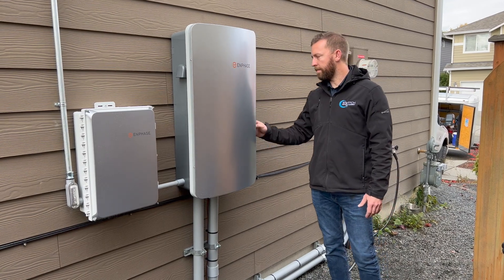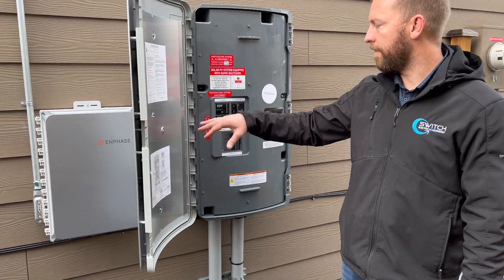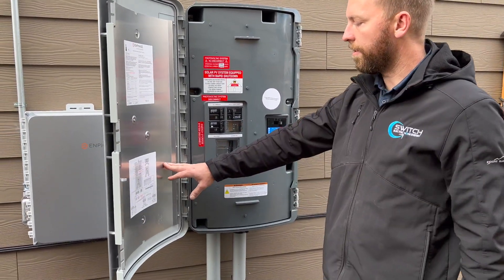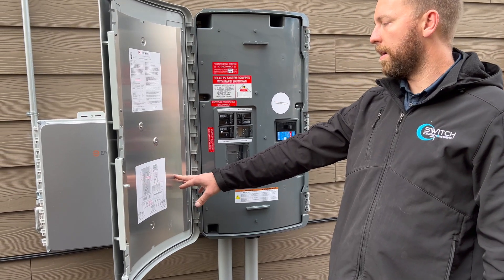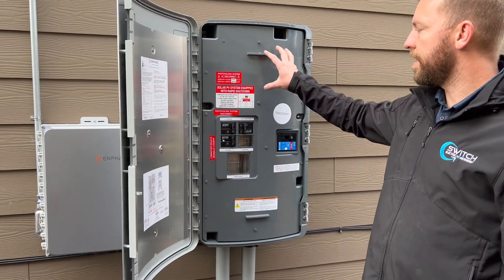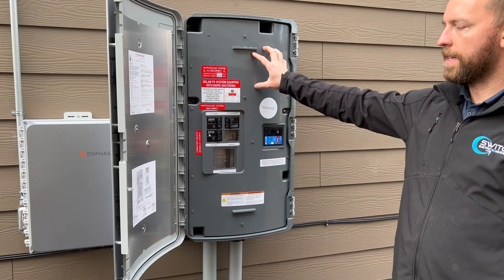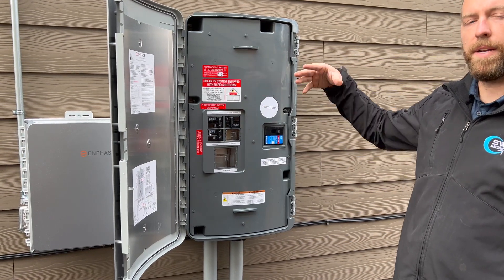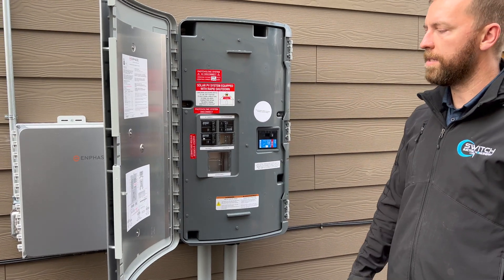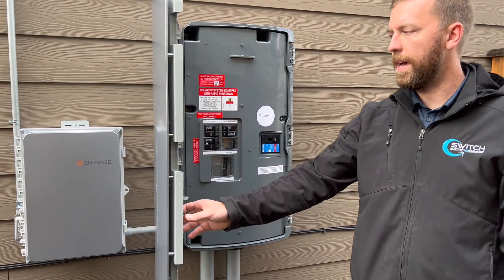We'll open this up and show you what it looks like inside. We have a few breakers — this is where the generator breaker is going to get installed right here, and it's totally upgradable for this customer in case he chooses to add it in the future. This Enpower switch also has a neutral-forming transformer built in, because microinverters don't generate a neutral. The transformer helps power the loads inside the house during a grid outage.